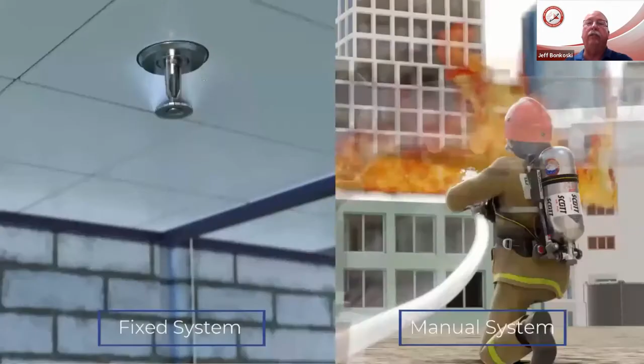When it comes out of a sprinkler head or through a fire nozzle, the molecules closest to the surface break apart. Now we've put a skin on the surface of each and every water droplet. We've chemically changed that makeup, and not only have we changed it, but we've changed the mechanism of cooling and extinguishing because of doing that. Yet inside of each water droplet are still millions and millions of these spherical micelles. To give you an idea of how many...